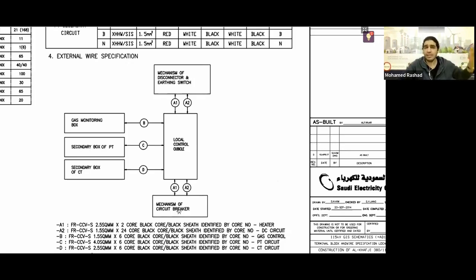Great, so are these the only things present in the GIS? No, why? The GIS also has the CT box, and the VT box, meaning the current transformer itself has wires coming out and connecting to your cell, and the VT has wires coming out and connecting to your cell as well, right? In addition to the SF6 gas gauges that we will see in the next slide, which are the meters that read the gas pressure of SF6.